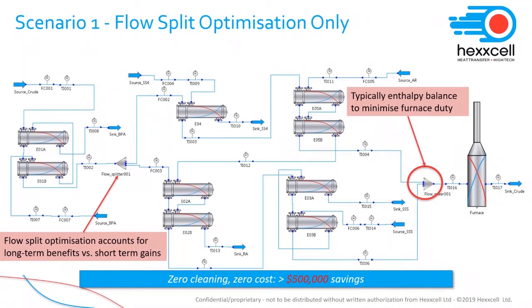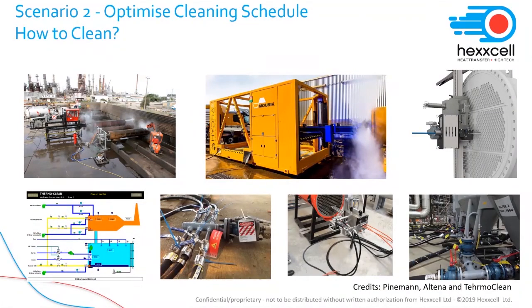This may not look like much, but it is a zero-cost option, and as you will see, when combined with optimization of the cleaning schedules, it can become very powerful. The next scenario that we looked at was the optimization of the cleaning schedule by considering optimal cleaning actions and methods. We provided prescriptive maintenance indications on which heat exchanger to clean, when, and with which method, mechanical or chemical. Chemical cleaning, as we have seen from the previous example, can provide mixed results, but if used properly can be very powerful as it provides a cheaper and quicker alternative to mechanical cleaning.